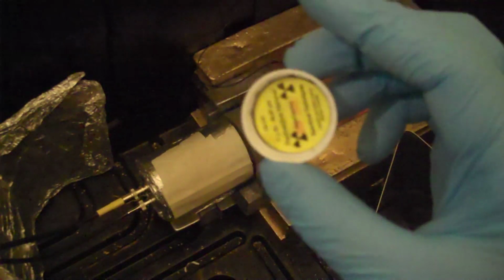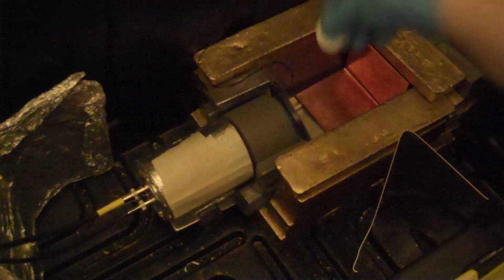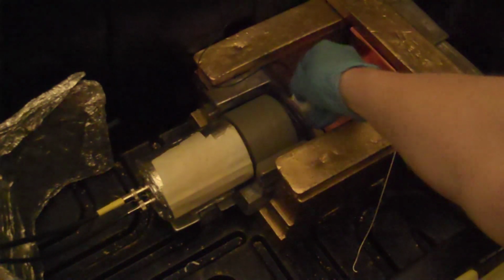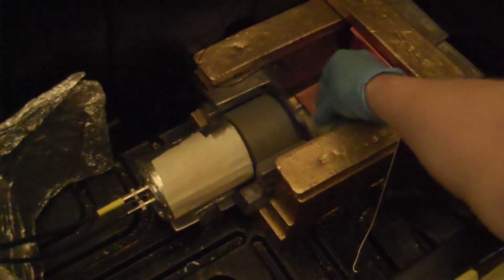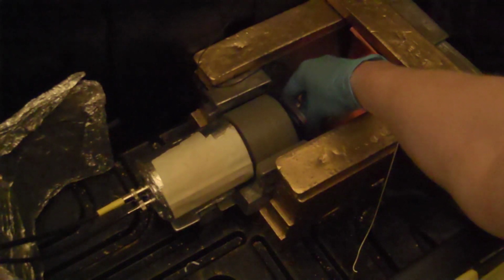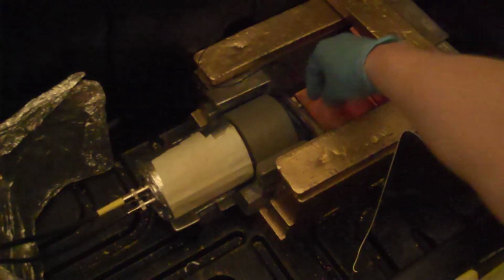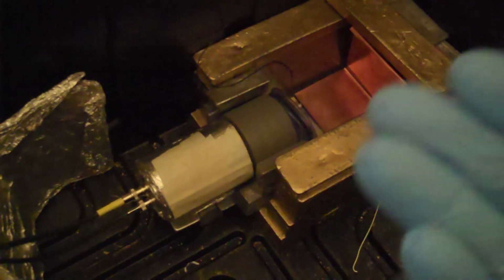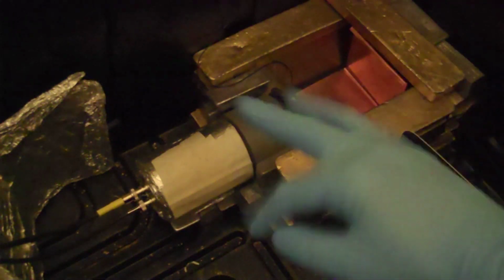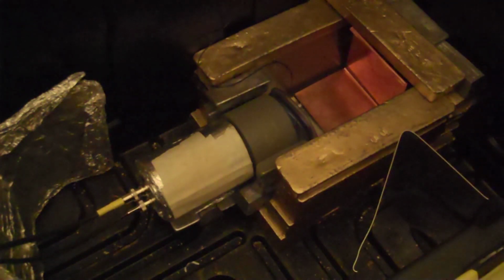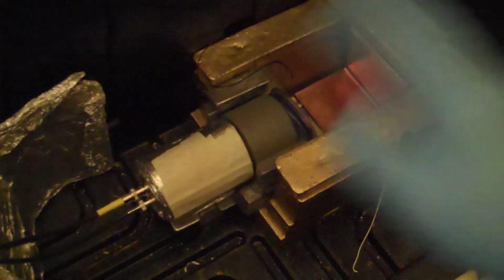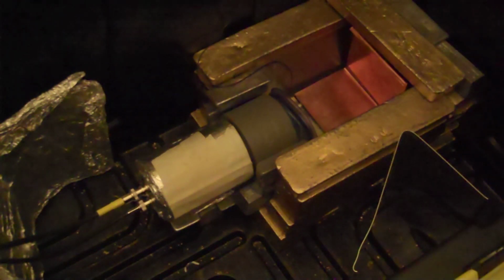So let's take this calibration source of cesium-137, and we'll put it right here. I use a piece of plastic here. The plastic and stuff is to block beta. Beta is kind of like a problem. Because beta radiation, what it does is it strikes all the metal here and it produces little X-rays all over the place, which can be quite a trouble. Now, let's calibrate with our unit. We don't even have to worry about putting the shielding back on for calibration.